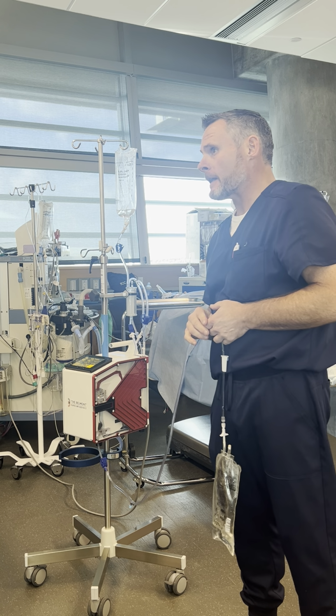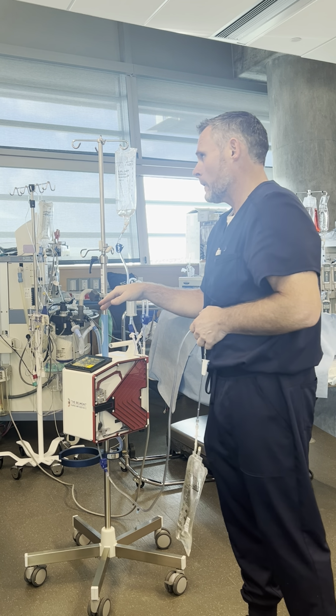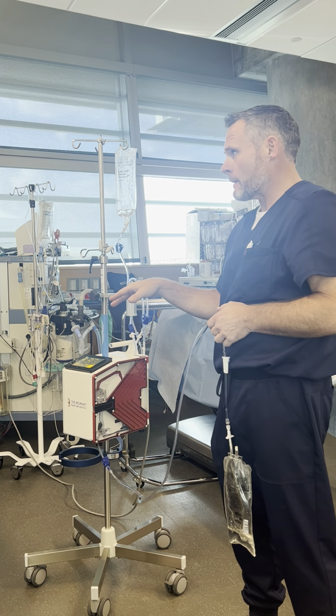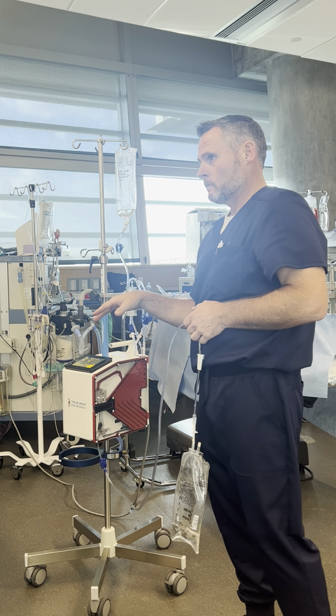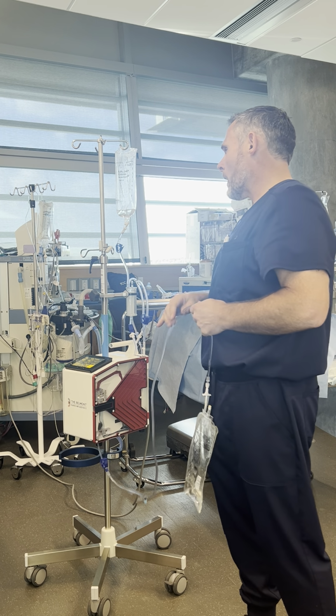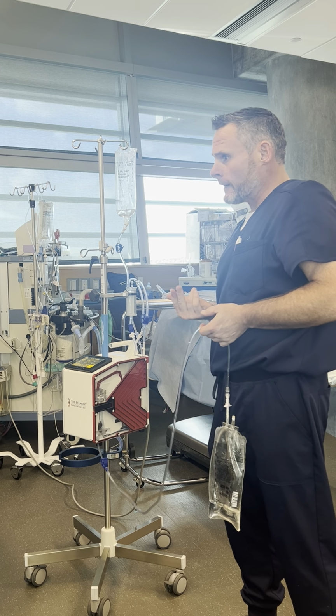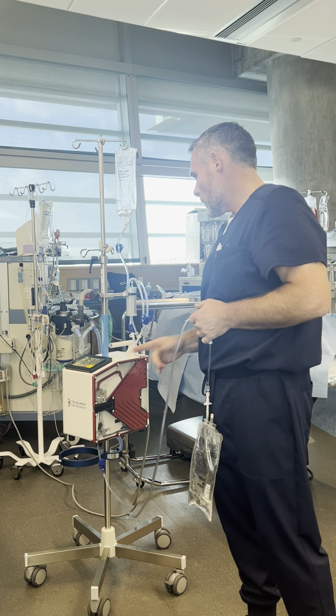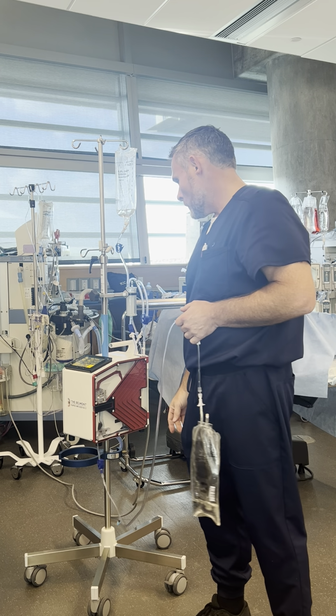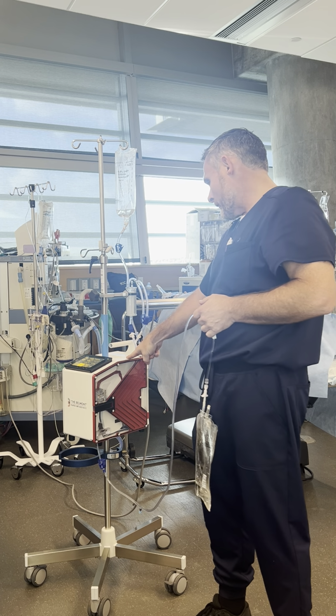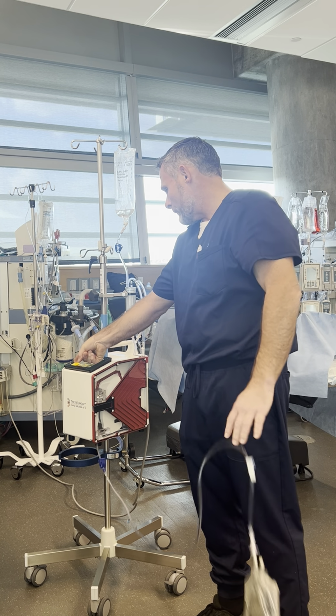Do you understand that? Because that's your biggest crossroads right there. If you understand that concept, you're going to be A-okay. Cool? Yes. Cool. Now, if you put a large bore on there, a 14 and higher, right? 12 French double lumen, large, then hit that 500. Go ahead. And then from there, you can go to 750 per minute. So press and hold and go to 750 per minute.